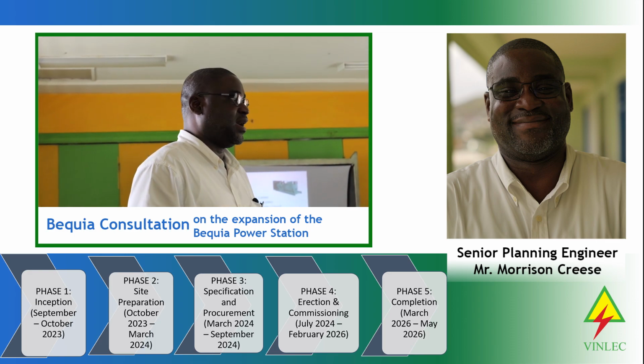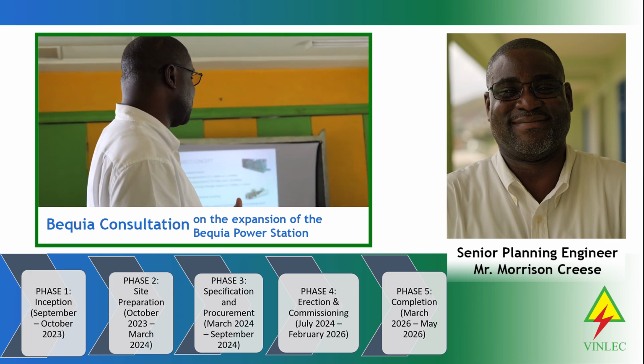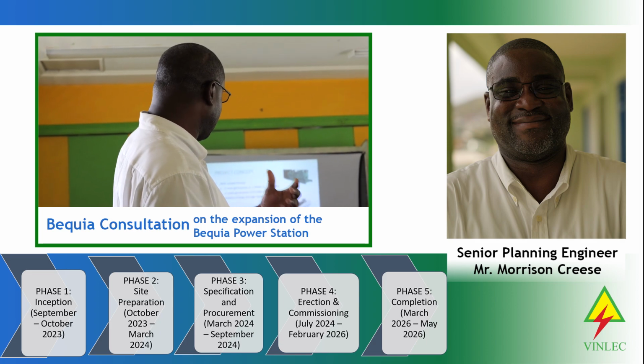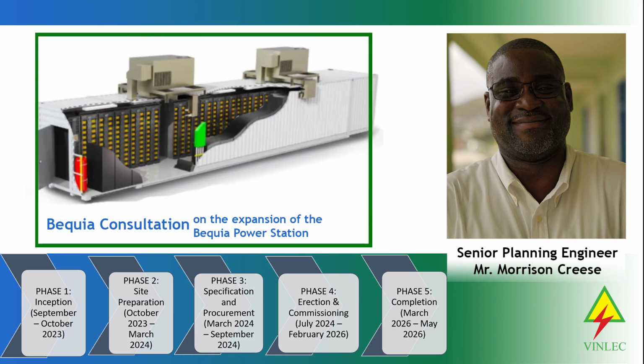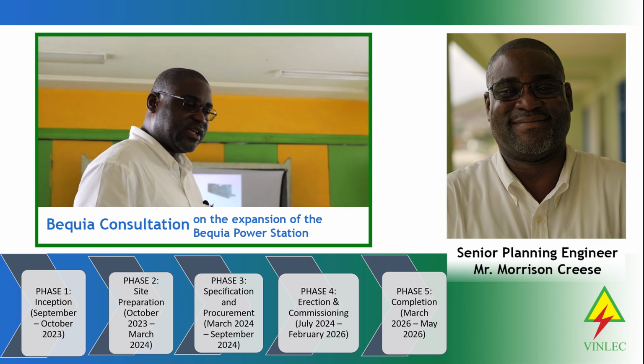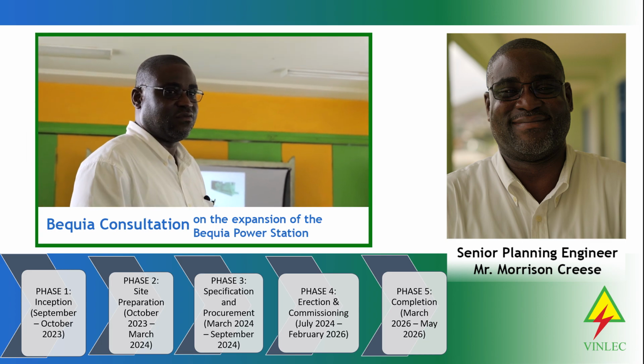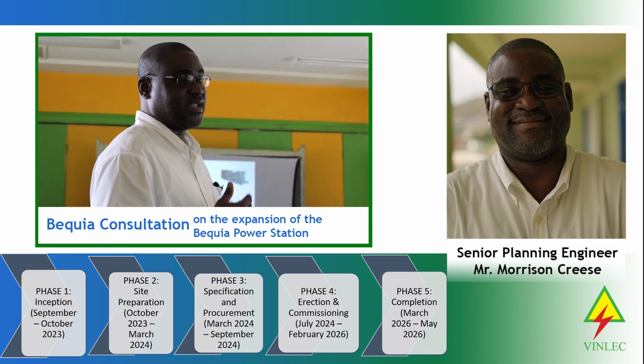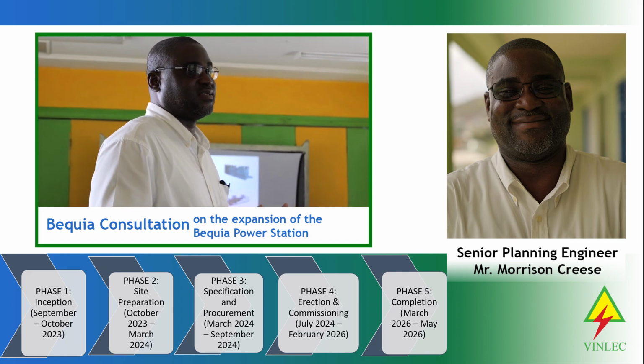In addition to the generators, the proposal is to install a battery energy storage system. Its main function would be to provide what we call spinning reserve. In short, spinning reserve means that if one of the generators were to disconnect from the system for any reason, the battery would instantaneously take up that load until we can start a new generator, improving the service we offer and the reliability of the system.